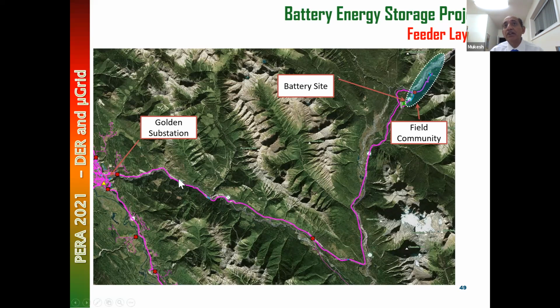So this feeder travels through a very rough terrain, and also it runs next to a railway line. So if there's an outage on this feeder, a mudslide or a snowstorm, if this feeder is lost, it takes a long time to repair it. It's not easy to dispatch a crew so far away on this rough trail. If there's a snowstorm, the road is not very good for the crew to go there. And then there's a railway track. You need to coordinate when the crew is working on an overhead feeder. You want to make sure there's no train coming by causing a hazard. So there's a lot of coordination.